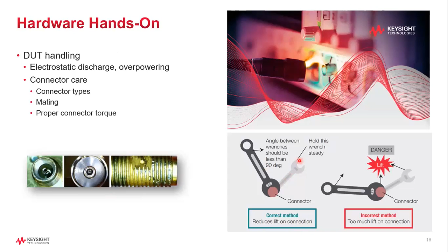See? Here's an example. When you do the torquing, you can reduce the error in the connection. So when you do the torquing, like this is a wrench, right? Or we call it another name, a spanner. Do you hold the whole handle, or where do you hold? The correct method is to hold at the end of the wrench and torque it. So you must have a torque wrench, not just a wrench, and know the exact strength to tighten the connector.